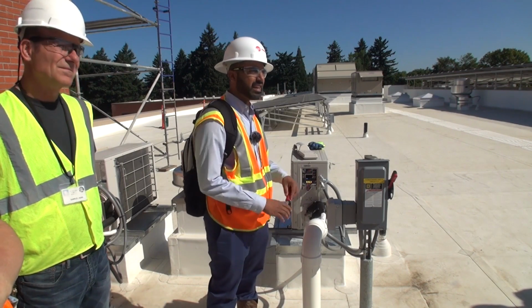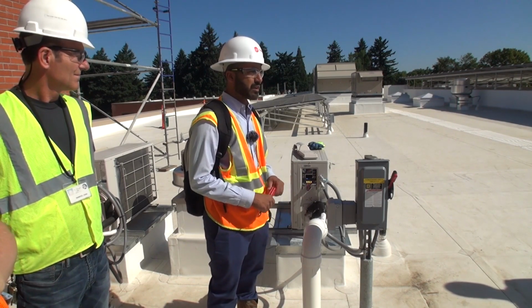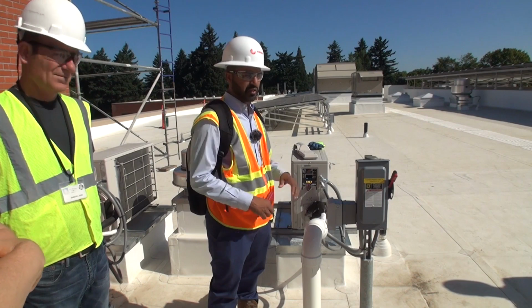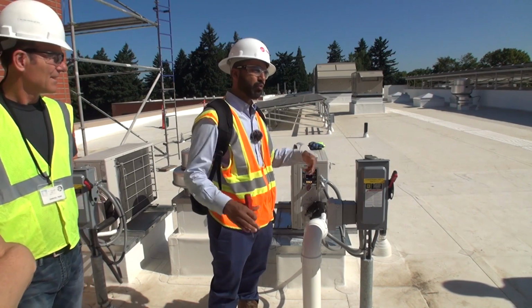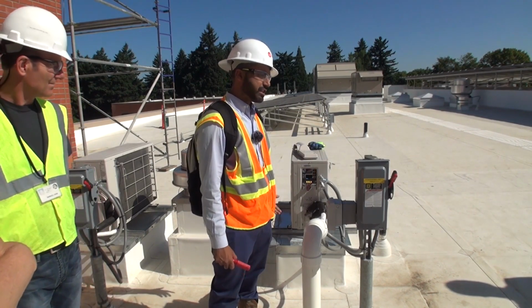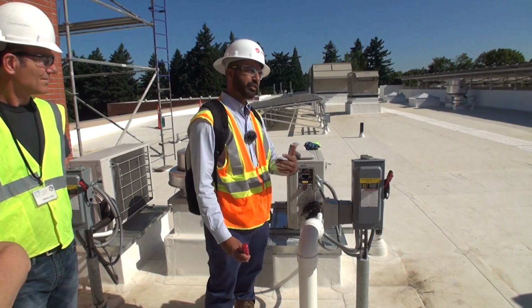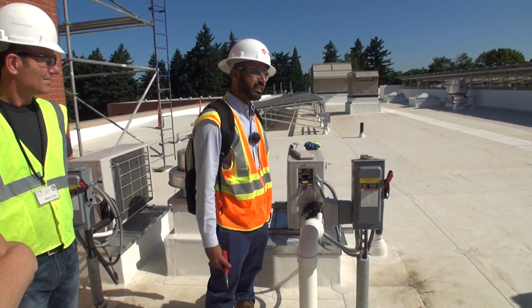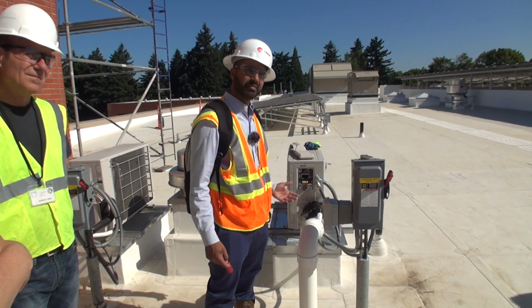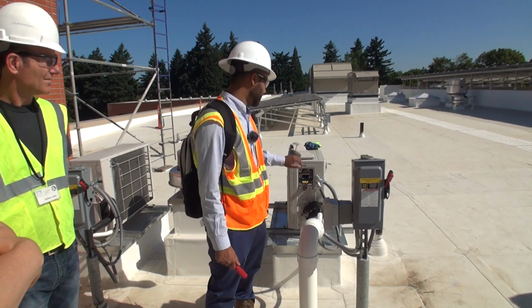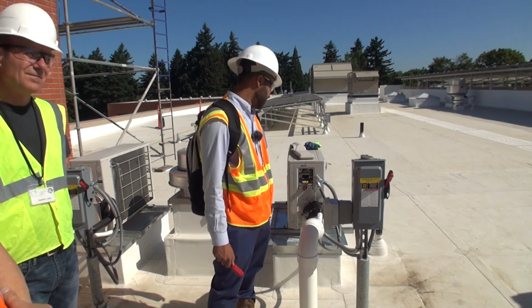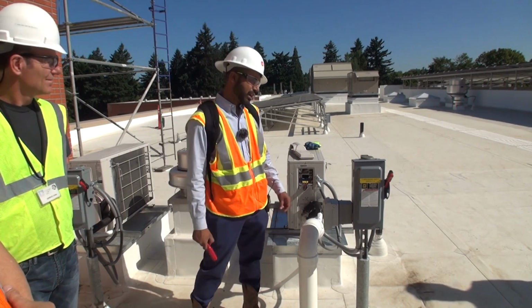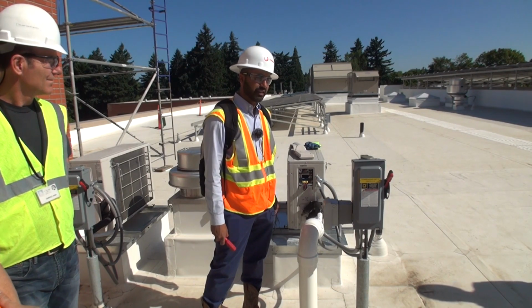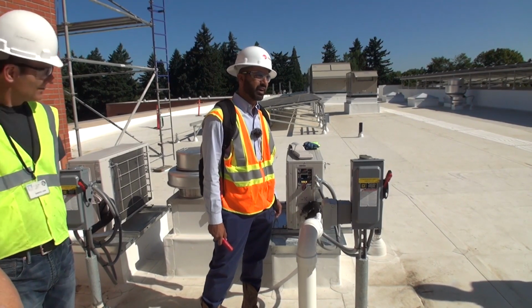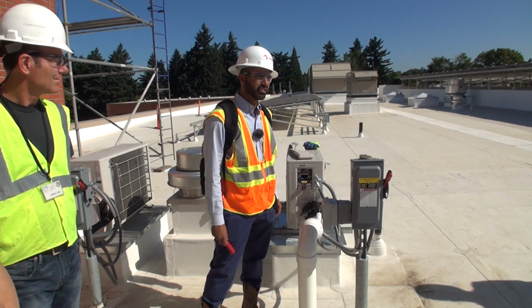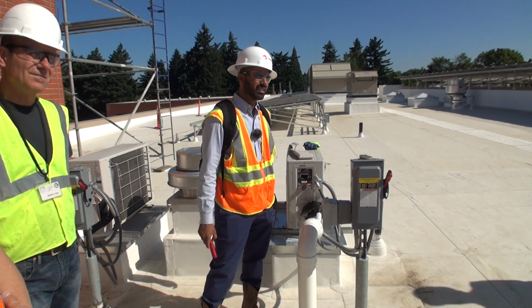That's a throwaway unit. It's not common for compressors to burn out on mini splits. It's usually the multi-head models, where oil gets trapped in one of the indoor units. Unless you're seeing a fan burn out on the inside and all the oil or refrigerant gets trapped in the indoor unit, you're not really going to see a lot of compressor burnouts on mini splits. If they do happen, it might be more prudent to just get rid of the outdoor unit and replace it. You can't put a cleanup dryer on them. In fact, that's not even allowed by the warranty. If you did put a cleanup dryer in, it would void the warranty. So it's best to just evacuate everything out.